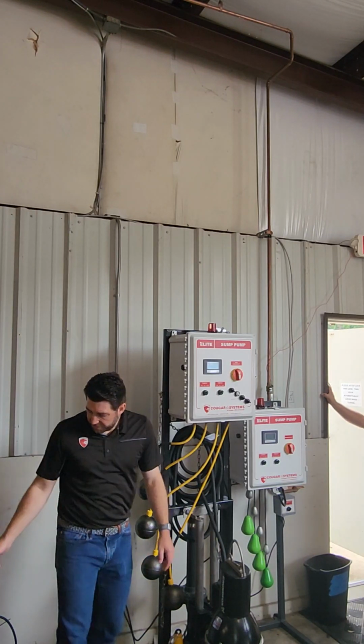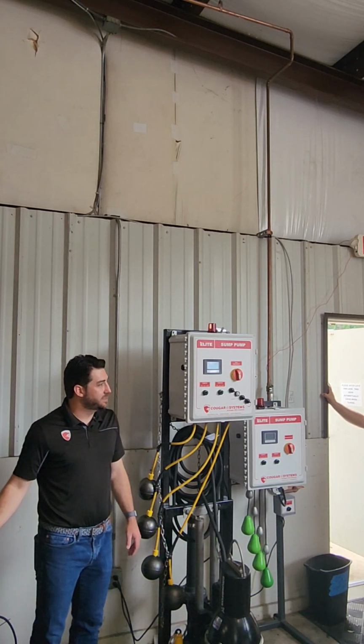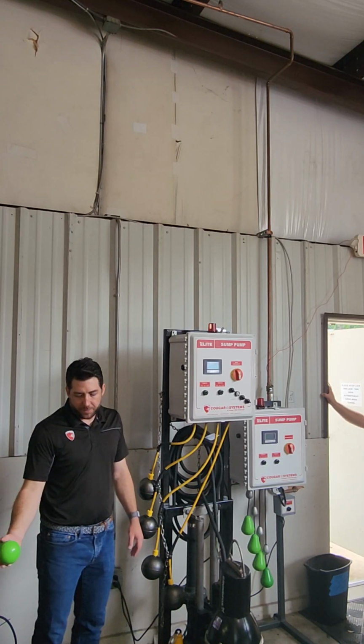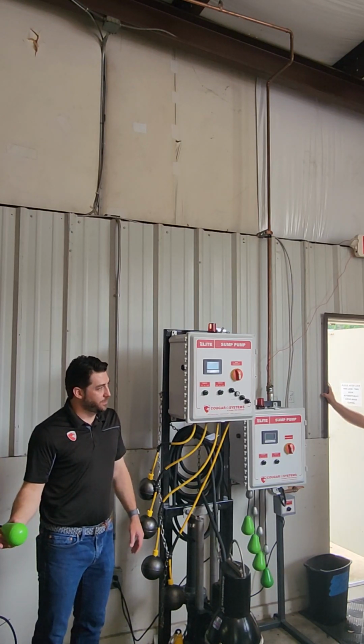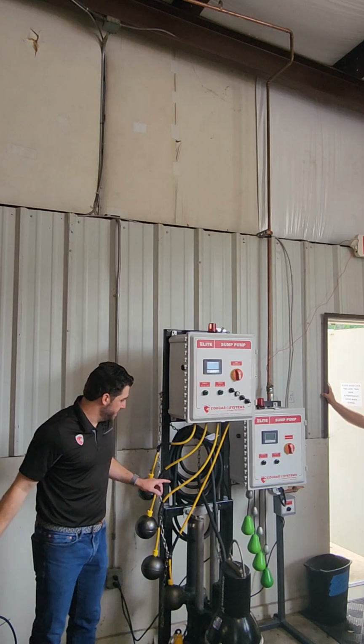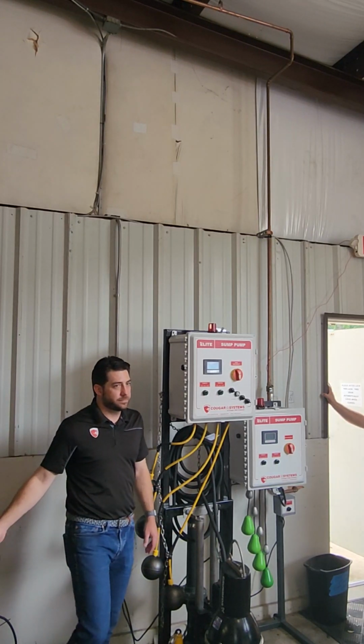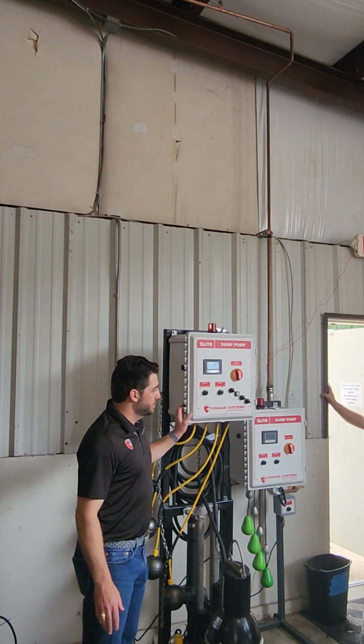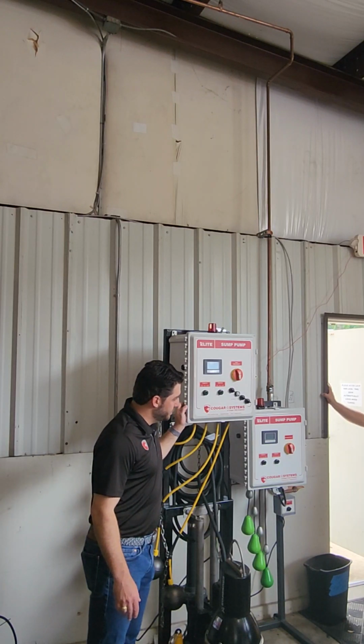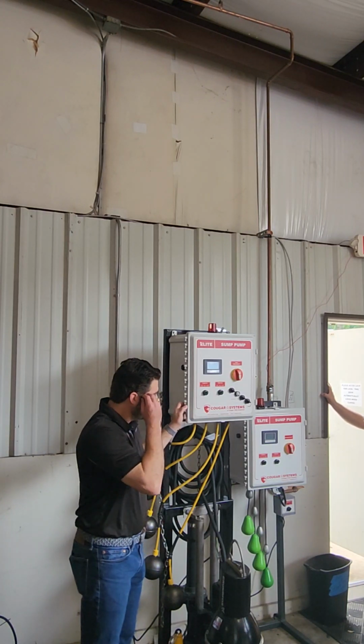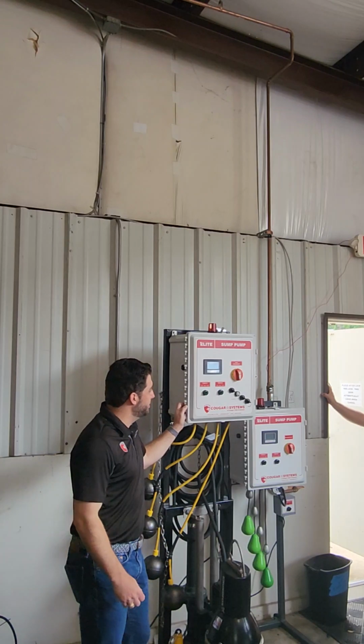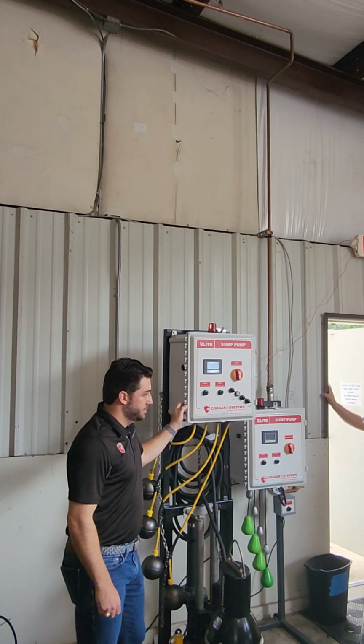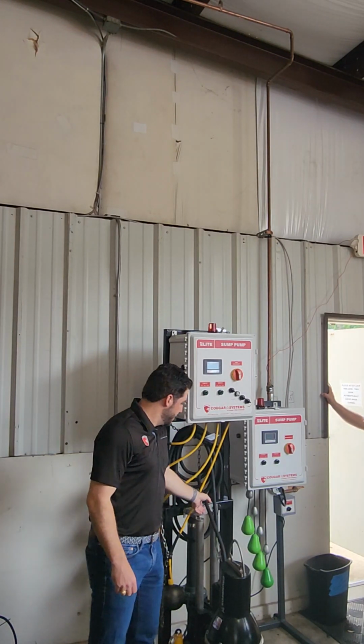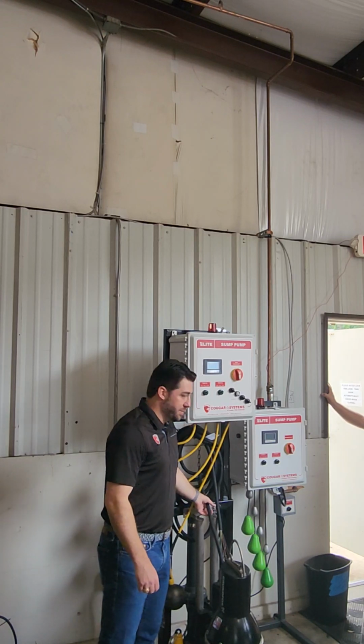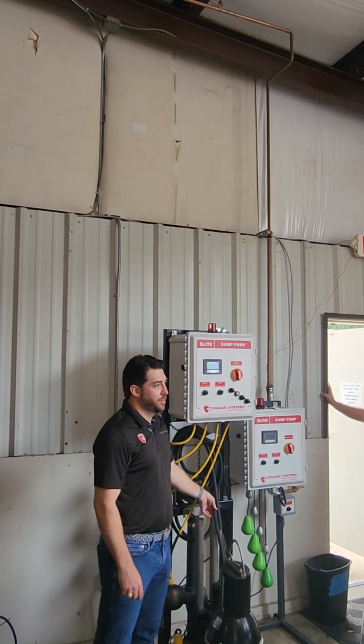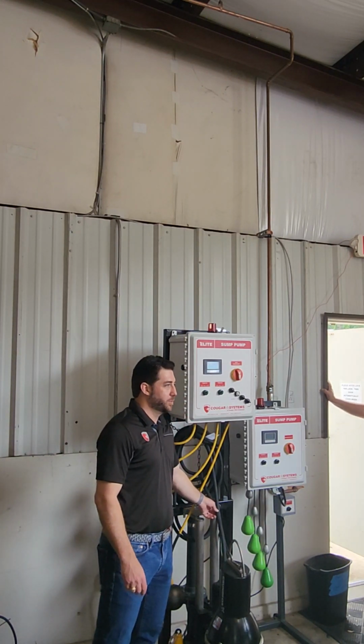Yeah, if these floats are getting eaten up or they're not lasting long, the high temp or the grease is really typically what does it. It heats them up, and these can handle it. Good deal. Before y'all make that decision, make sure y'all remember the size of the wire. Yeah, so you gotta make sure the conduit is big enough to fit the wire. Good point. And ideally, if it's a new pit or you're rehabbing it, you'd want separate conduit for the pump cabling and the floats.